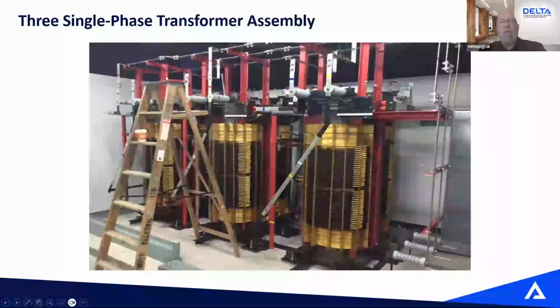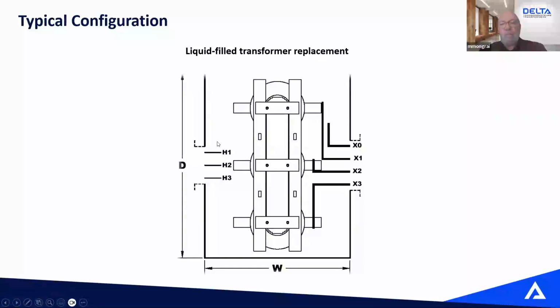This is what it looks like once it's fully reassembled. Of course, the three single phase transformer option will take more footprint in your electrical room. So in those cases, we need to have the space. It takes about 40%, 50% more footprint than a standard three-legged core transformer. But sometimes moving equipment in the electrical room and using this option will be much more cost efficient than ripping half of the building down to bring in a standard three-legged core three-phase transformer.